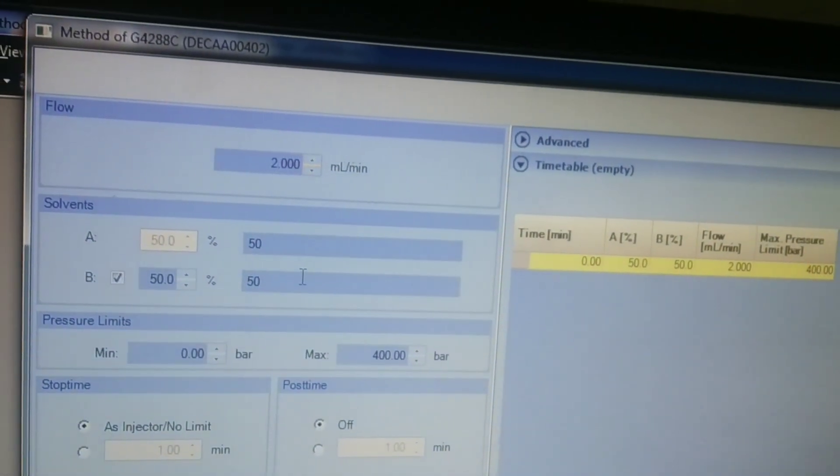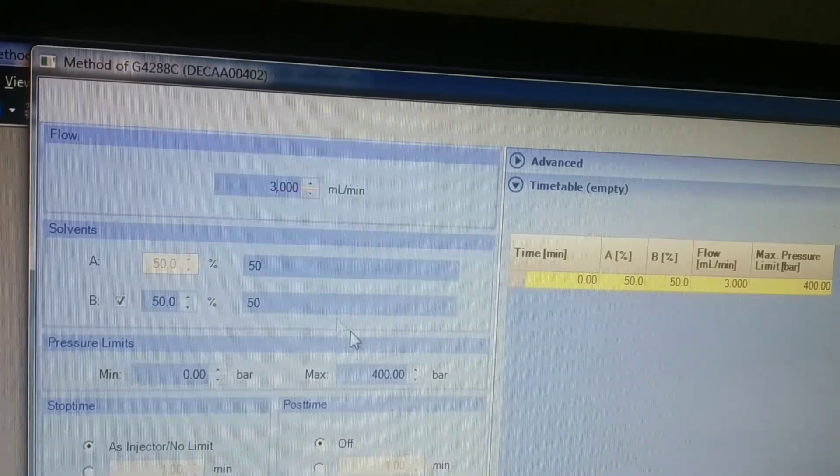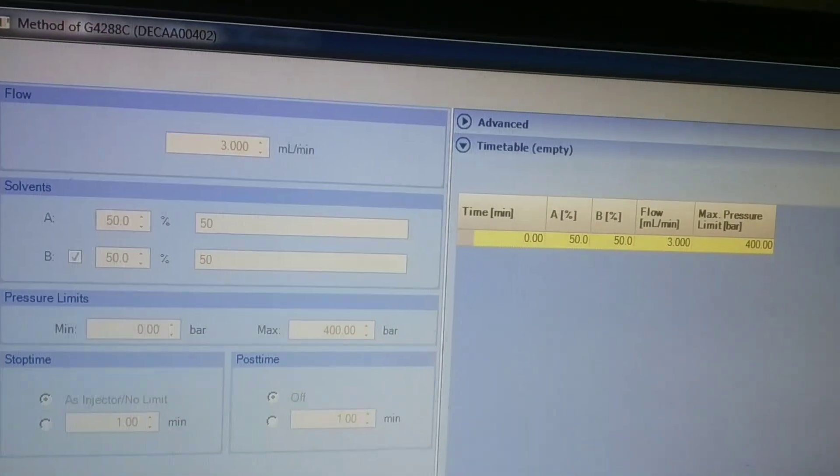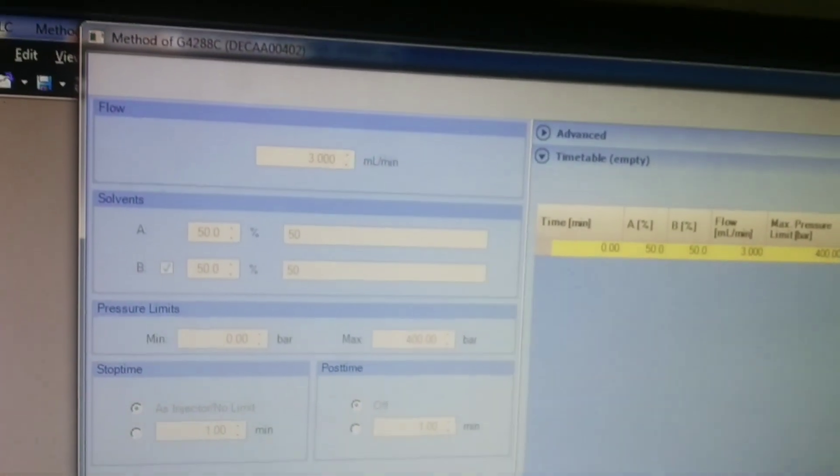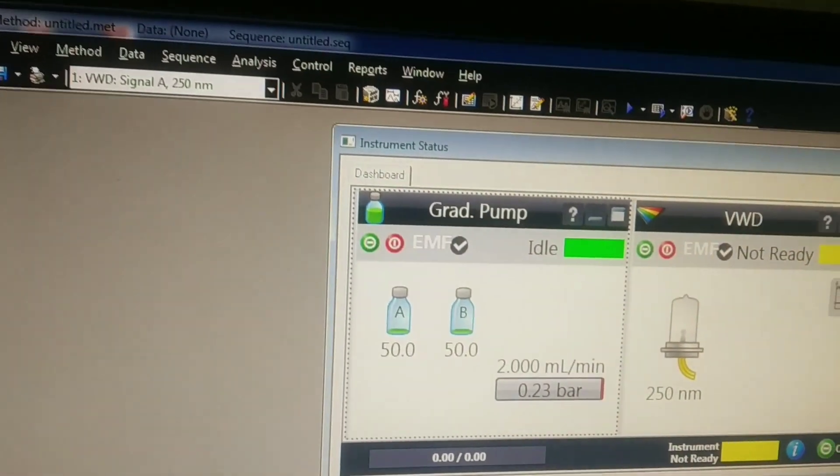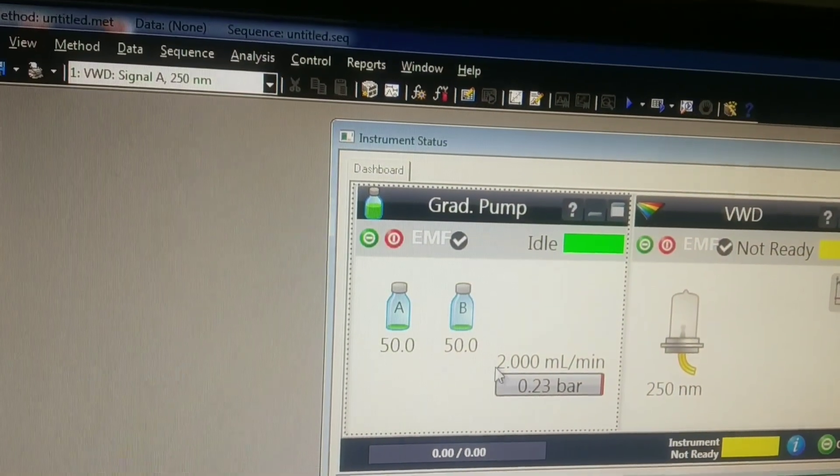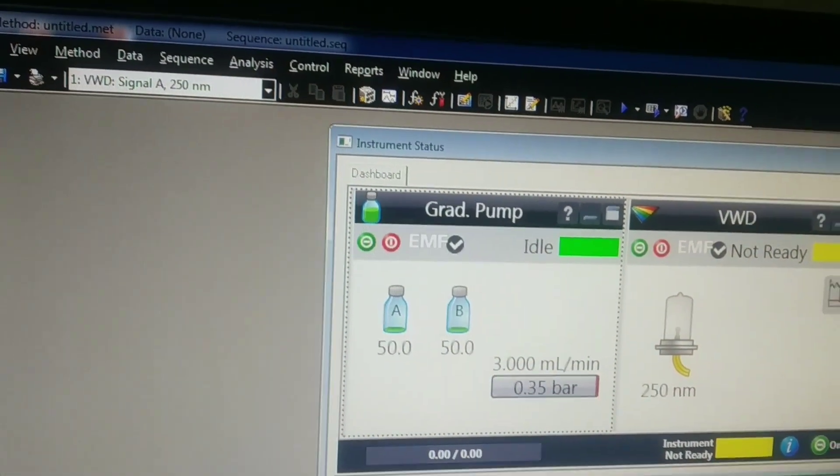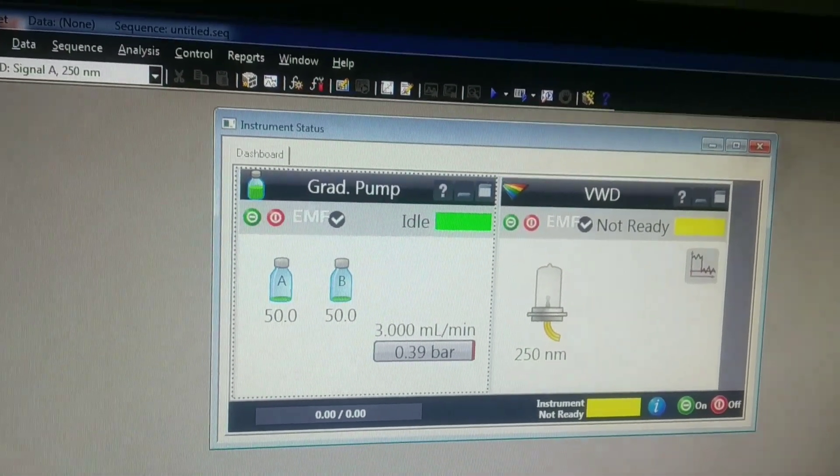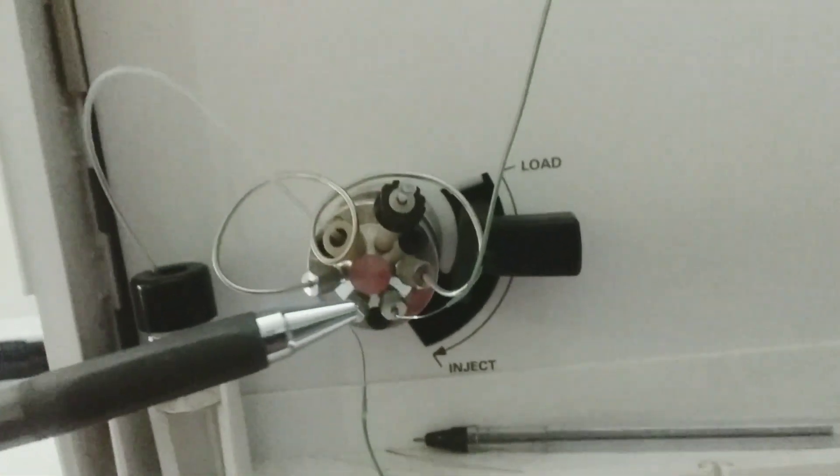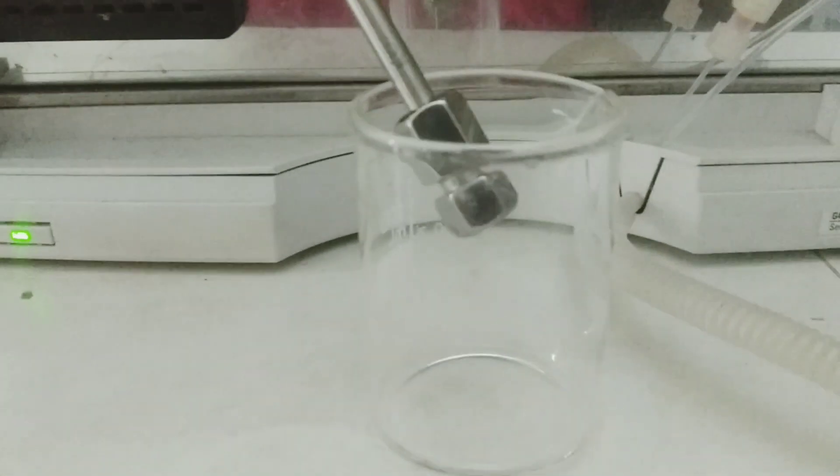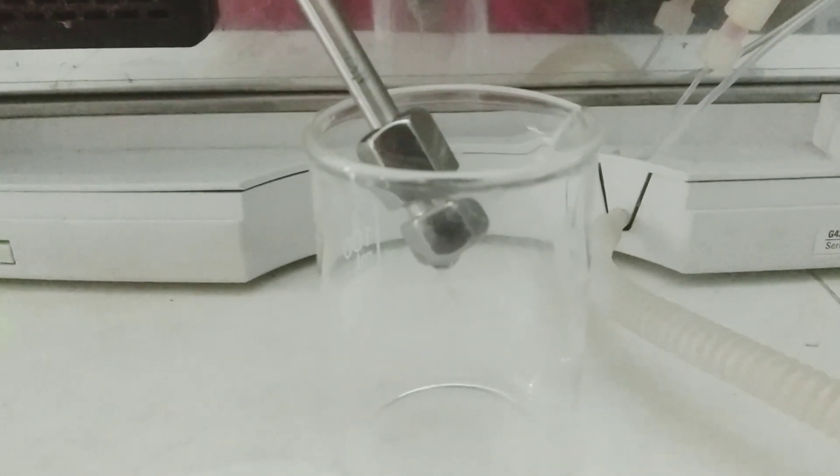As we see, as I increase the strength of the solvent combination, better cleaning of the pipelines as well as the columns takes place. I repeat this cleaning, purging, and washing with slight increments in the flow rate. You can see the cleaning solvents moving through the pipeline from the pump through the injection port into the column and getting drained out. With this, the column will be completely cleaned of all the unwanted particulate matter.